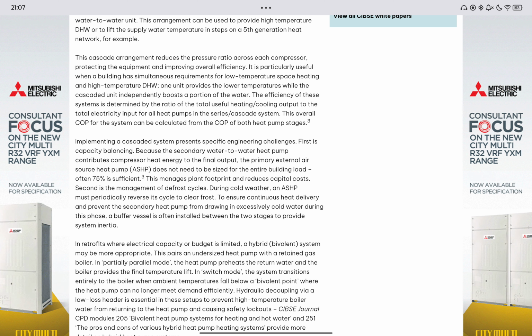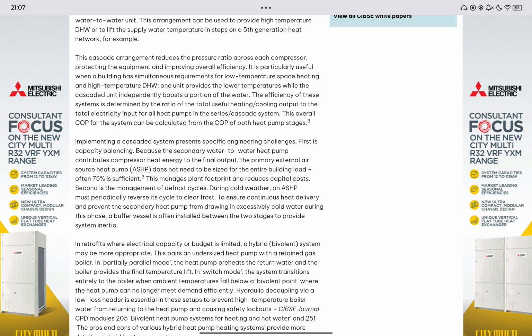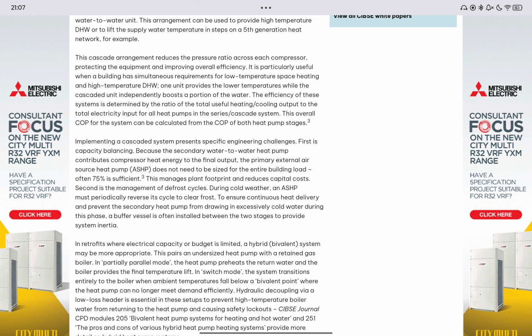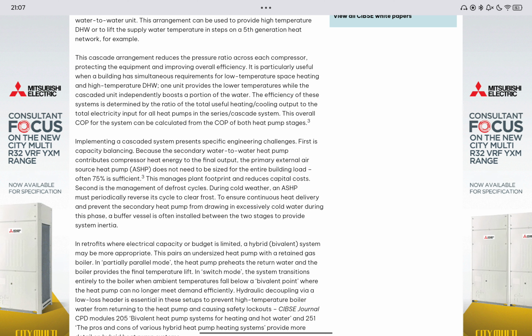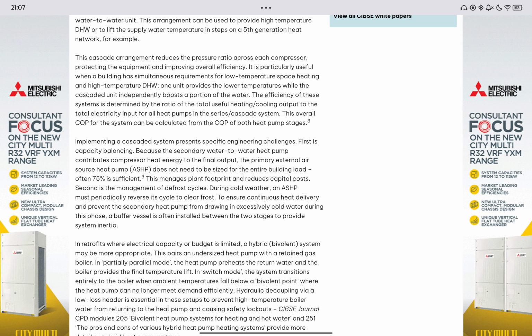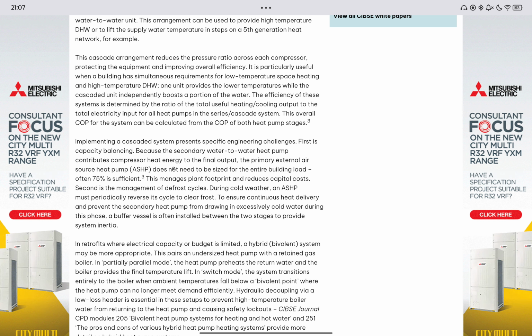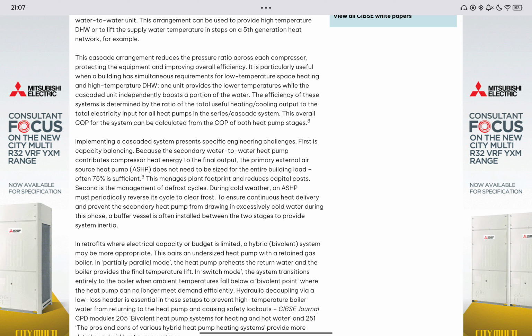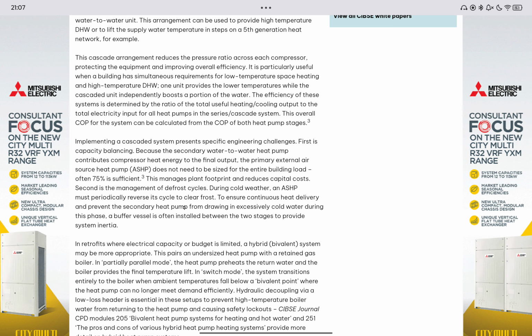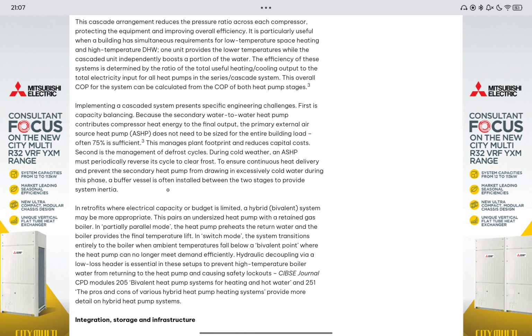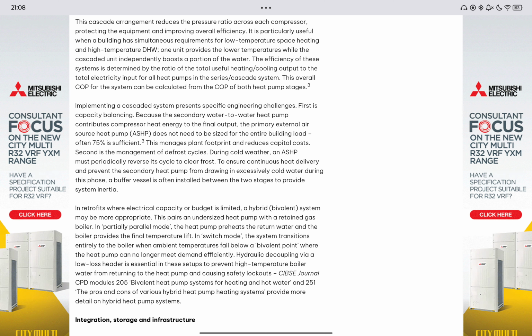It is particularly useful when a building has simultaneous requirements for low temperature space heating and high temperature DHW. One unit provides the low temperatures, while the cascaded unit independently boosts a portion of the water. The efficiency of these two systems is determined by the ratio of the total useful heating or cooling output to the total electricity input for all heat pumps in the series cascade system. This overall COP for the system can be calculated from the COP of both heat pump stages. Implementing a cascade system presents specific engineering challenges.